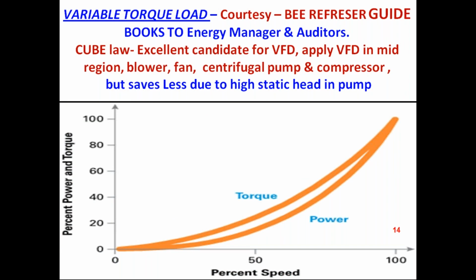Variable torque load is an excellent area for an energy auditor in a given industry, where the cube law or the affinity laws for fans and blowers can be applied. Any amount of RPM reduction, say a 5% reduction in RPM by optimizing the revolutions per minute for the given equipment, will give almost 14% power savings. A 10% reduction straight away gives 27%. This is what we want to utilize in industry.